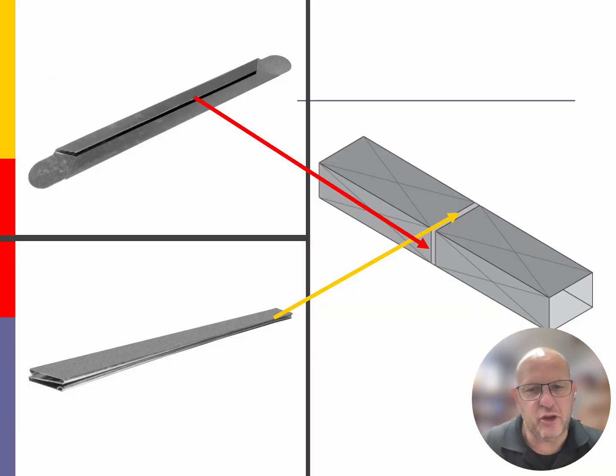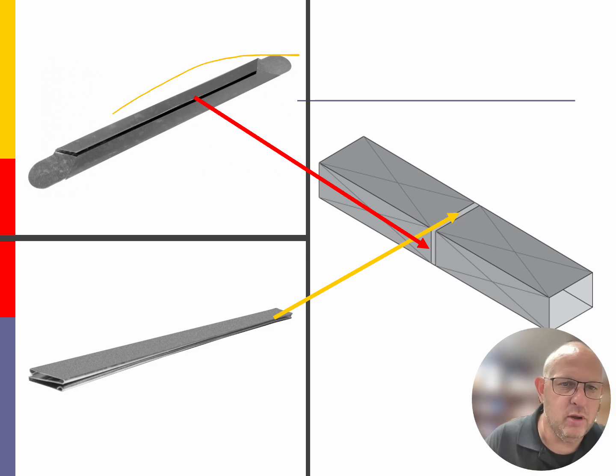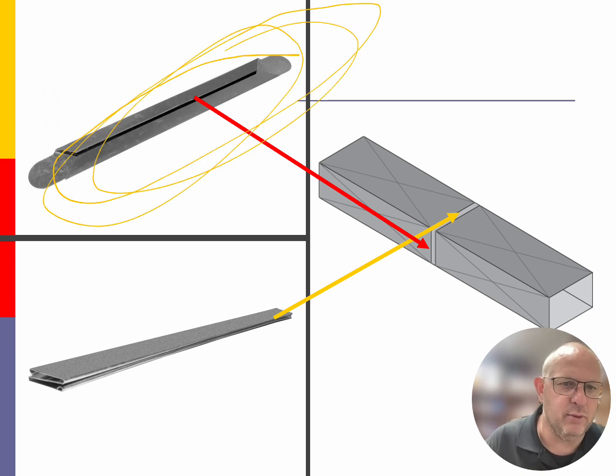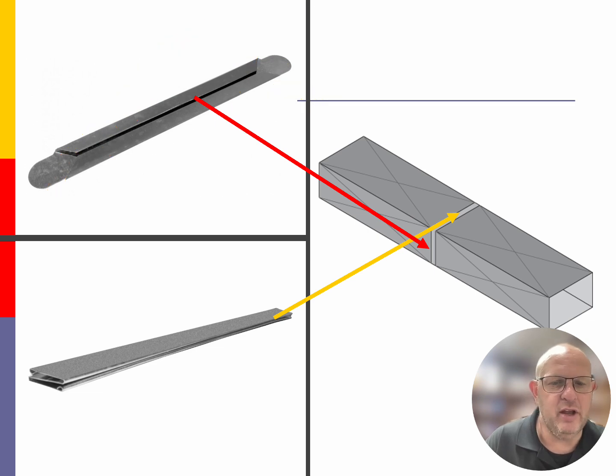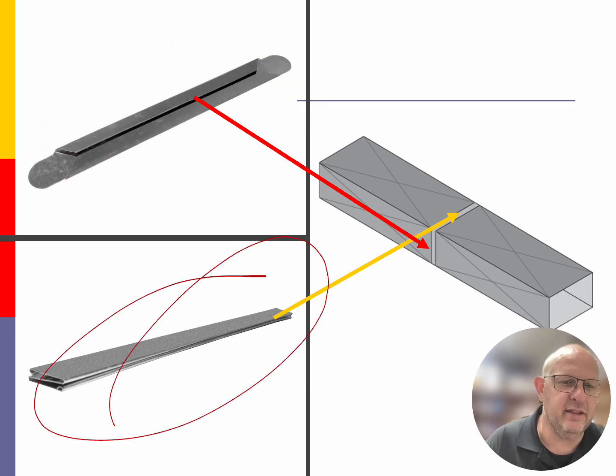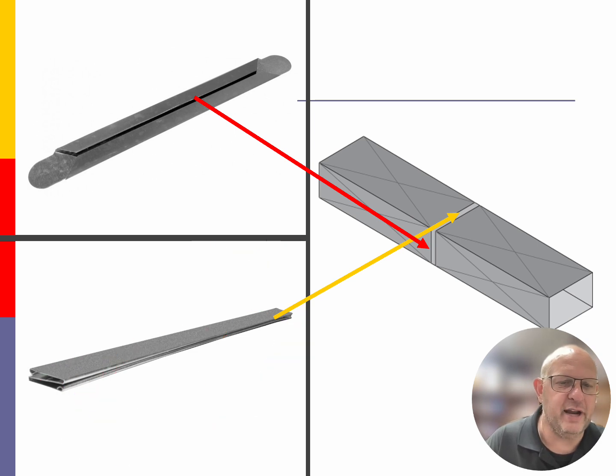So this is just another picture of the drive cleat, which is the red arrow. Okay, so this is my drive cleat right there, as you guys can see. That's my drive cleat. And then my S-lock is right there. There's my S-lock. Okay, the arrows are actually going to be showing you the different areas that those fittings are going to be placed on the rectangular ductwork so that we can put that ductwork together.